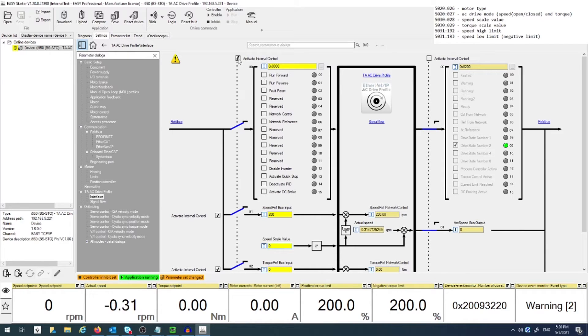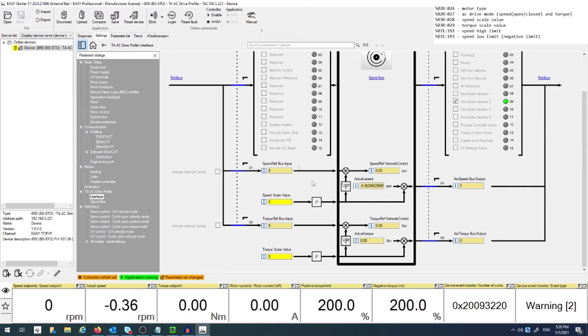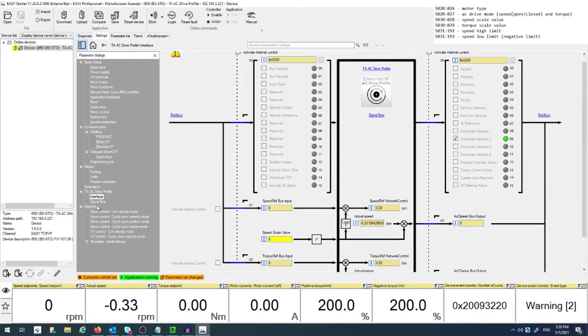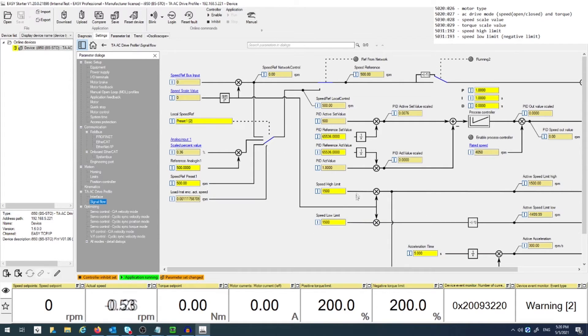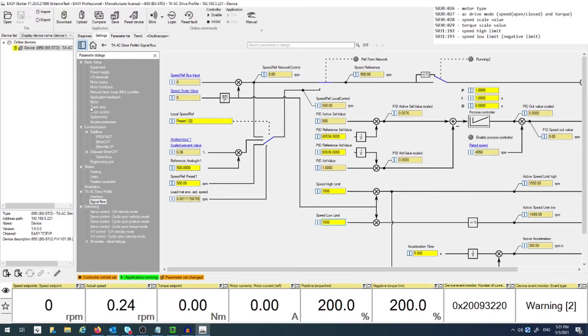Two other parameters you should take notice of are the speed high and low limits, found in the signal flow subsection. If you have a scale value that goes above or below this limit, the motor will not go to that speed, so update these values appropriately.